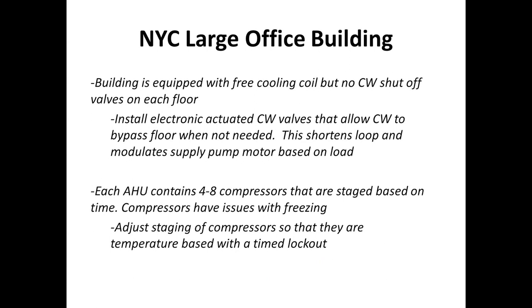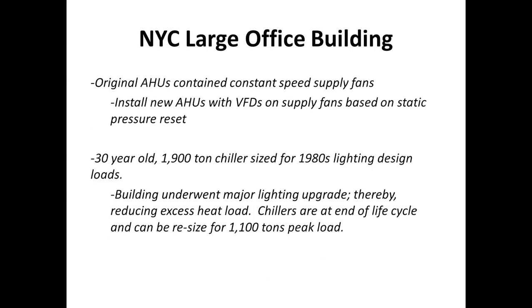What we did was we changed the control logic. So these compressors were staged based on supply temperatures, and one compressor was left on for so many minutes, and if conditions still weren't met, then the second one kicked on. This helped with energy efficiency in the sense that it actually cooled the building. It prevented the units from freezing up, and it was a logical way to meet space conditions.